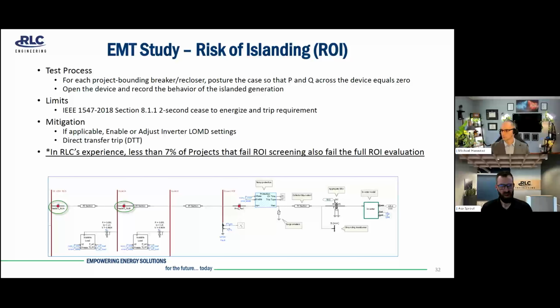And our mitigation strategies for this are, if it's possible, we would adjust the inverter loss of mains detection settings, which are used for essentially ROI mitigation. I would note that, and if I haven't noted it before, these inverters are typically going to be black boxed, meaning that all the control functionality is there, but what we can actually see and what we can actually control within them is very limited because manufacturers want to protect their IP and not provide that to everyone.